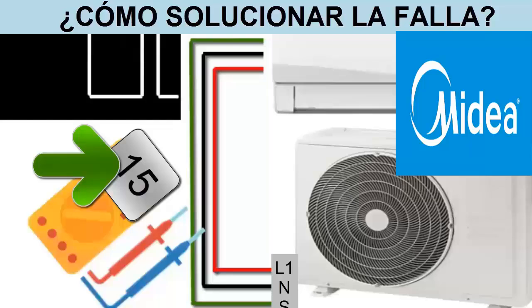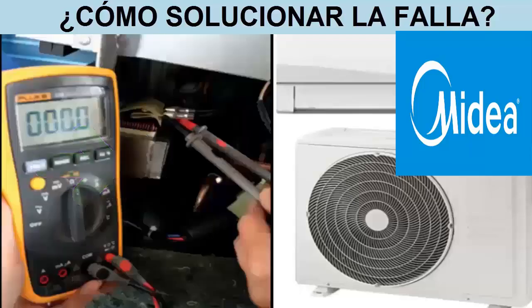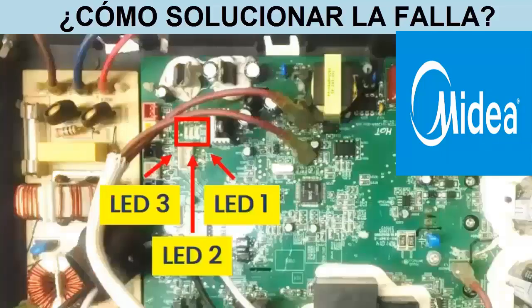10. Before making any replacements, it is recommended to measure the electrical continuity in the reactor located in the outdoor unit, using the multimeter on the continuity scale. 11. If you have access to the outdoor unit's board, check if it is functioning. Locate the LED diodes and see if they light up.